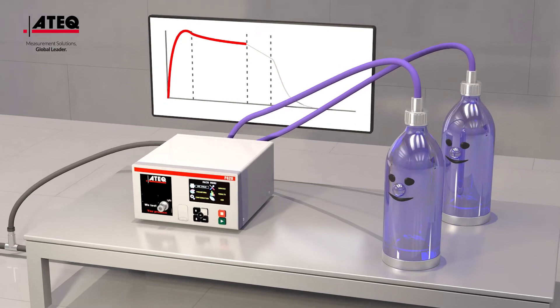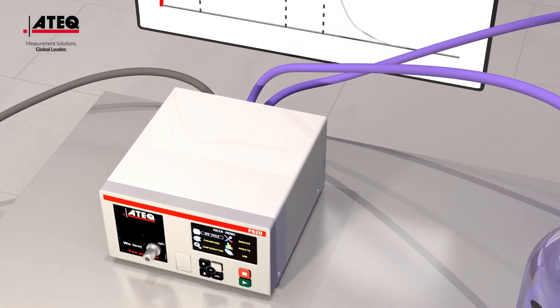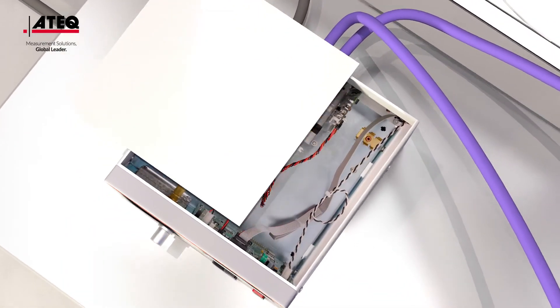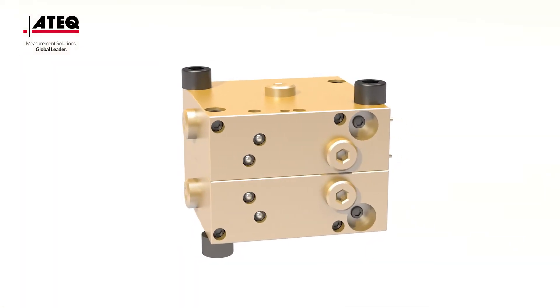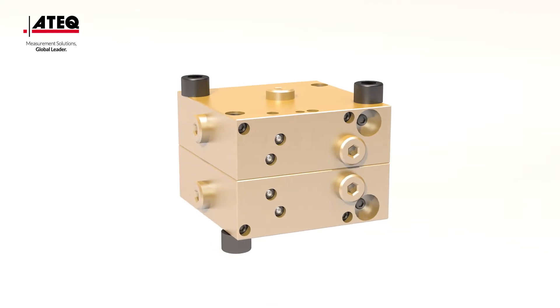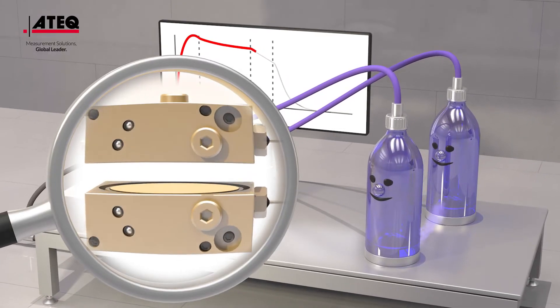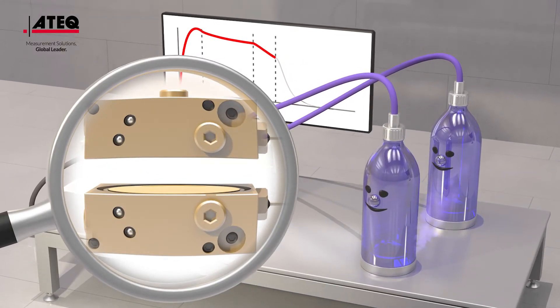The following test time compares the pressure between the test circuit and the reference circuit. If a leak exists in the test part, the pressure drops. The differential sensor diaphragm will then move and this movement will be converted to leakage values, such as cubic centimeters per minute.